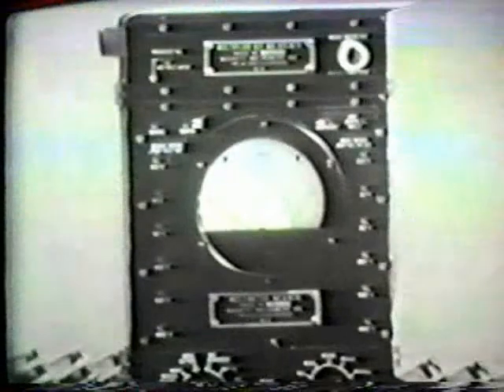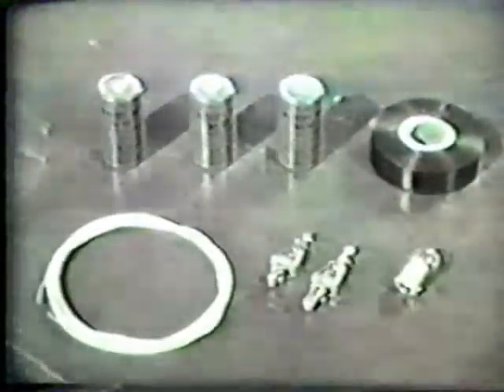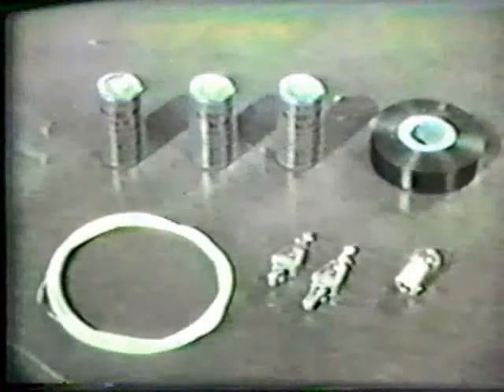The multimeter, when properly used, will help solve both simple and extremely complicated electrical troubleshooting problems. The other two items used in troubleshooting, the jumper wire and continuity test light, are simple compared with the multimeter. The jumper wire is merely a fairly long length of insulated wire with an alligator clip at each end. The continuity test light is another device which you can make for yourself. The materials required are flashlight batteries, a bulb, a length of insulated wire, 2 alligator clips, and a roll of insulating tape.